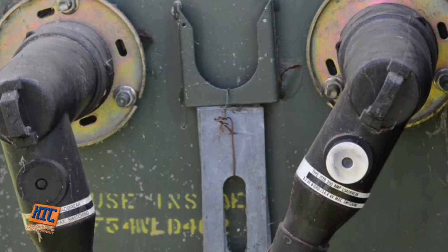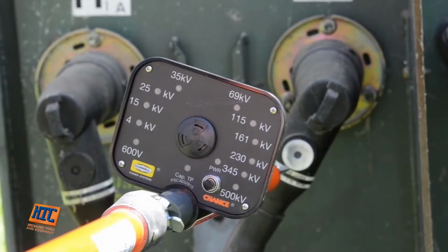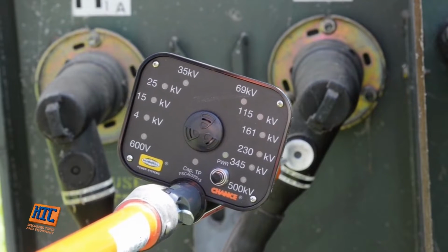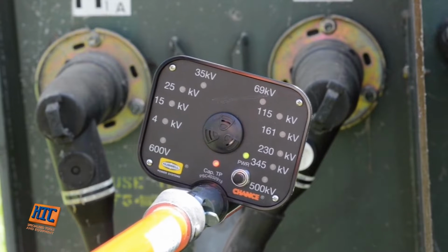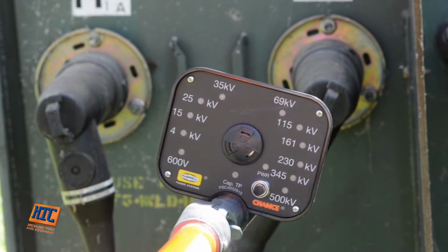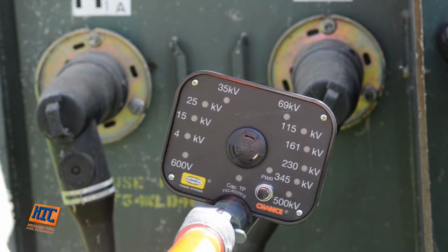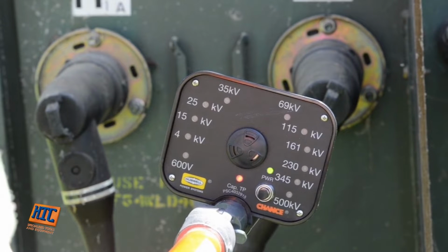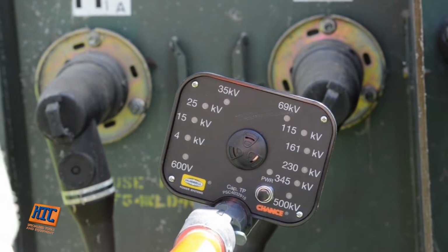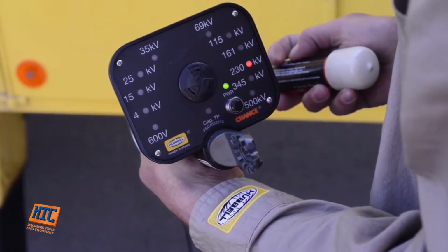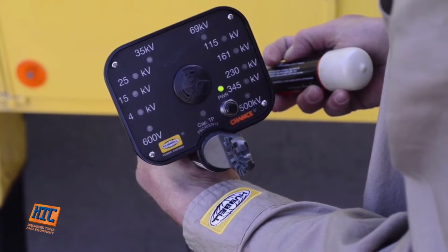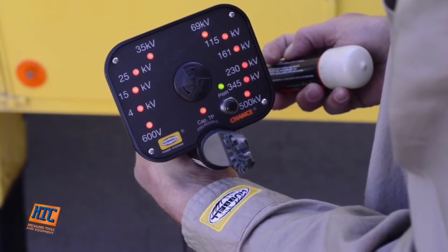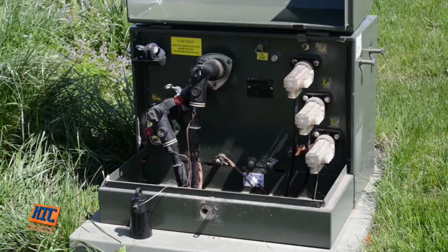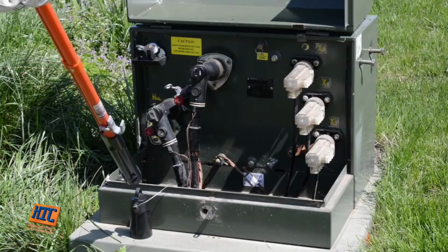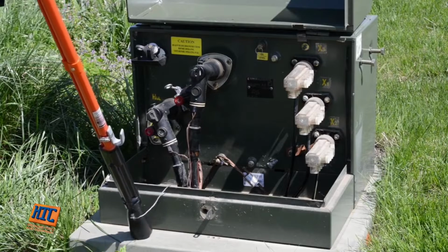Then, with the RV mounted on a universal hot stick of appropriate length for the voltage, and having replaced the shepherd hook on the front of the RV with a straight test probe, simply contact the elbow test point. Notice that the LED marked TP for test point blinks and the RV beeps, indicating the presence of voltage. After each use, verify the RV is fully functional using the voltage indicator tester specified in the instructions provided with the RV.